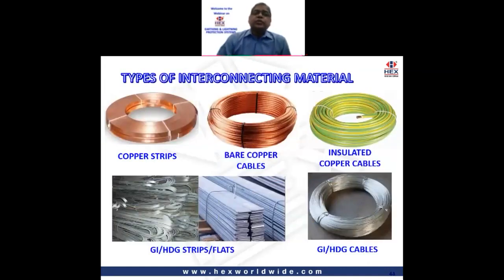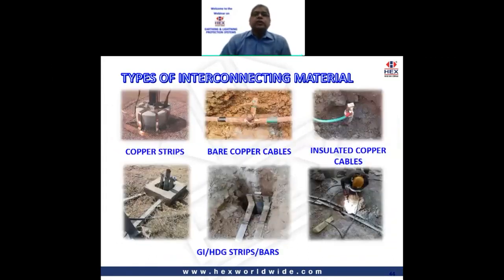These are just some types of interconnecting materials that can be used: copper strips, bare copper cables, insulated copper cables. You must be knowing all about this. And these are some applications of these to connect the electrodes to the grid. You know, different types of copper, insulated, or GI are used.